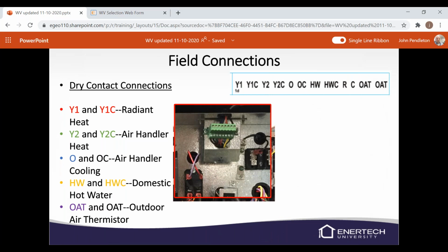Low voltage, this is your removable terminal strip here. These are dry contacts, so no power goes through here. It's just an open or closed circuit. So Y1 and Y1C, that's your radiant heat call. Your Y2 and Y2C would be an air handler heating call, which would be a higher heating temperature. The O and OC, that's your cooling call. HW and HWC is your domestic hot water call, and OAT are your outdoor air temperature sensors. That's where they're going to be mounted into.